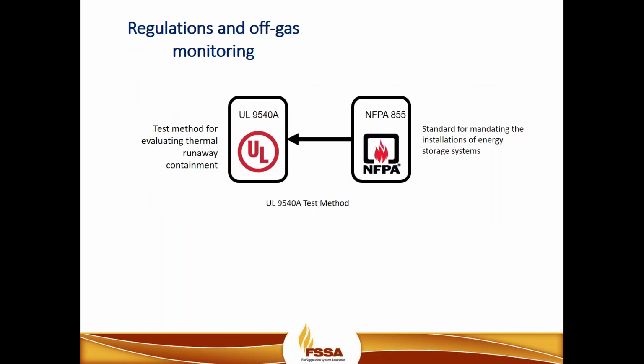When we look at the codes and standards, they're pretty much in their infancy, but they are developing at a rapid pace. NFPA has a number of committee members that are looking to enhance and continue the work that NFPA 855 has brought forth. And of course, the UL 9540A test standards are the test methods for all lithium-ion batteries. But we're even seeing new code adoptions or new code language being introduced into documents like NFPA 75. Even the International Building Code or International Fire Code is looking to adopt new language to look at energy storage systems and the risk associated with that.